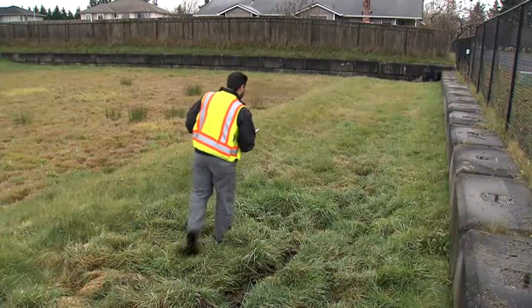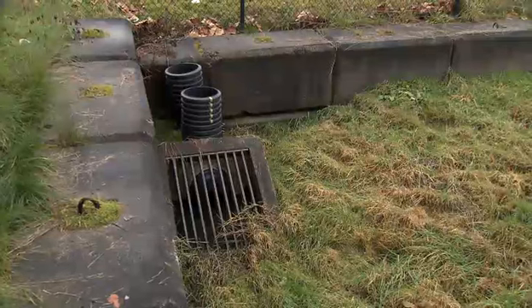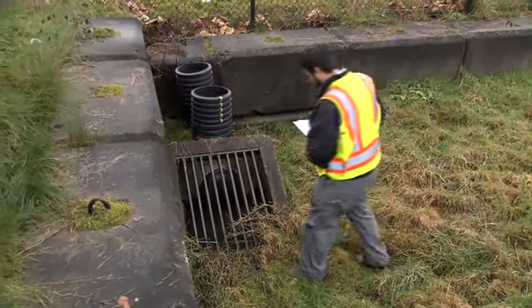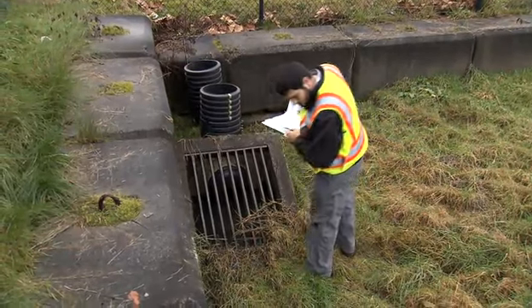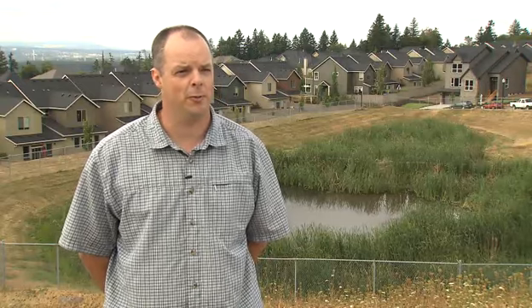When you start a facility inspection, typically the first place you would start is the inlet pipe — the pipe that goes into the facility. You want to make sure that it's free of sediment and debris. There might be floatables, some trash, pop cans, things like that. And then what's at the end of the pipe? Is there sediment buildup there? These are typically the first areas that start to go bad. Typically there's large rock at the end of an inlet pipe — has that been filled up with sediment? If so, that needs to be removed because that's the first place invasive species like cattails and blackberries will start to grow.